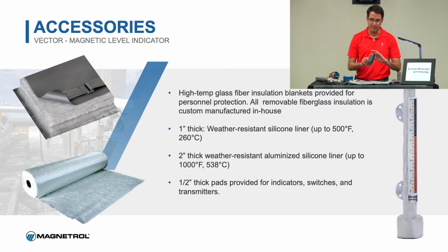We're also, if the temperature exceeds, I believe it's 250, we're going to put the insulation pad behind the indicator so it protects the indicator as well. Typically in that case, if it's just like 250, we're not going to do the blanket. We may not even do the blanket a lot of times if you guys don't need it. Okay? But I recommend it for protection of personnel.